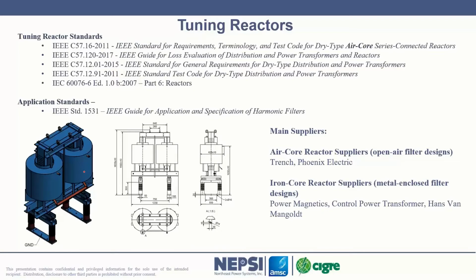A key characteristic of iron core reactors is that the magnetic flux stays inside the core of the reactor. That has some advantages, and it is why we use them in the metal enclosed harmonic filter banks, because we can't have an external magnetic field. So somebody was asking a question about the voltage and current induced on the fence of a substation that might have a harmonic filter. It will be because air core reactors are being used, and we're going to talk about this in a second. Air core reactors are being used. These are North American suppliers. I'm not sure if they're located also in Australia, but I'm sure you have suppliers local there also.